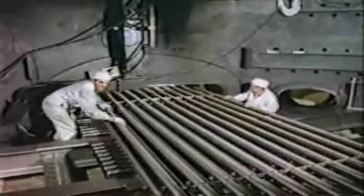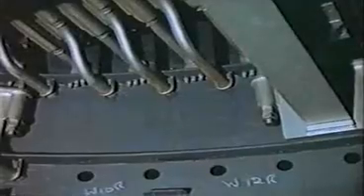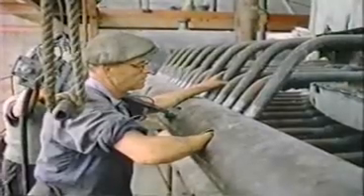At the base of each boiler is a horizontal cutout to permit passage of the cleaned coils. The coils are hoisted into position by an internal winch and are stacked in a stepped pattern for maximum heat transfer efficiency. Hot carbon dioxide gas from the reactor core flows over the tubes from top to bottom of the boiler at a pressure of nearly 140 pounds to generate steam within the tubes. The ends of the tubes pass through holes pierced in the boiler shell to connect to external steam drums and headers.